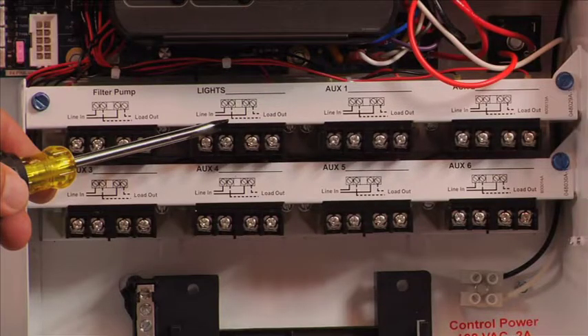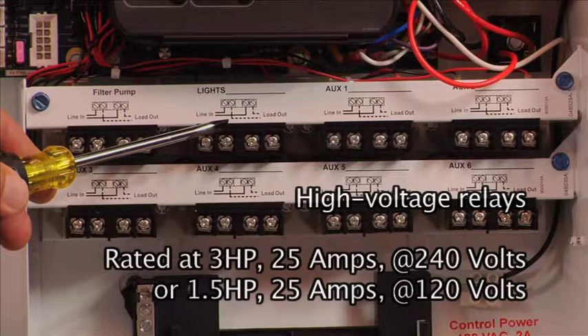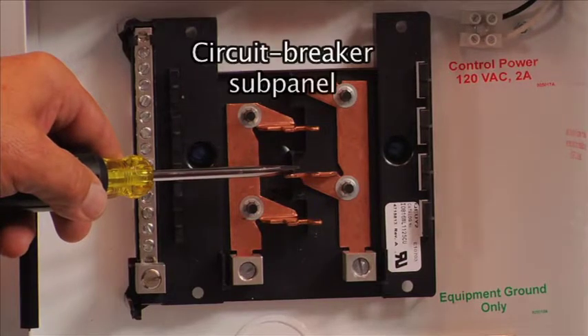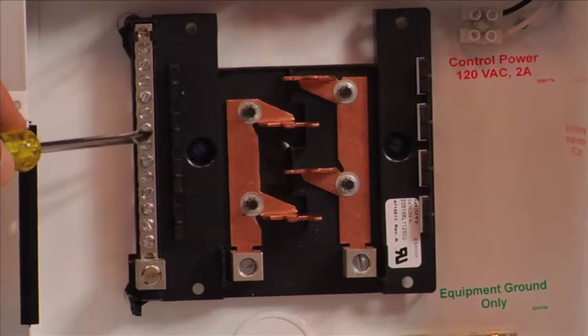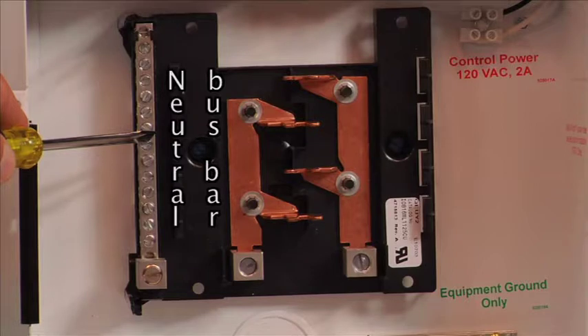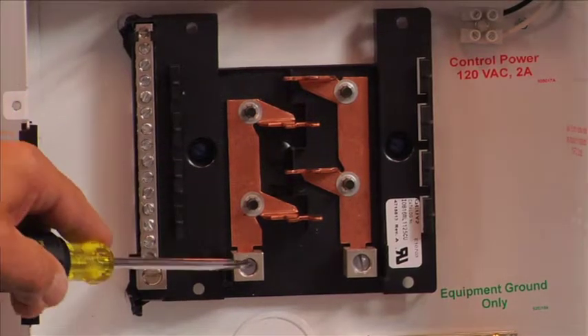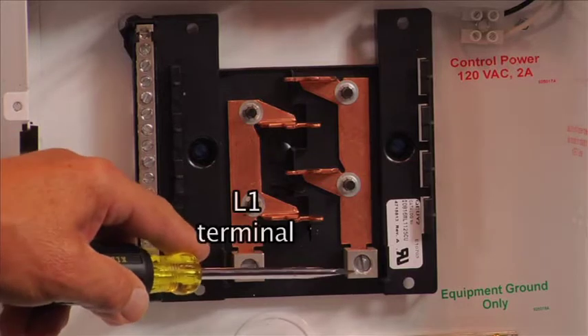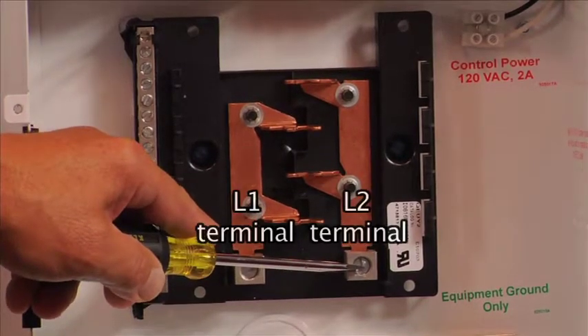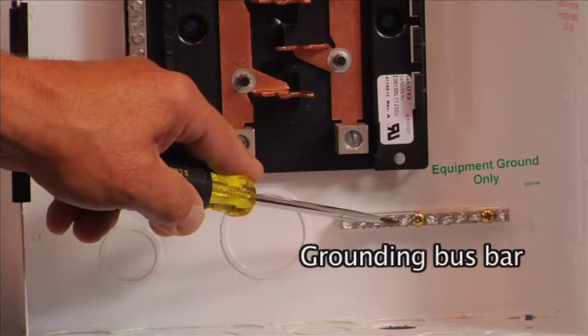Below the PCB are the high voltage relays. These relays are rated at 3 horsepower 25 amps at 240 volts or 1.5 horsepower 25 amps at 120 volts. Below the high voltage relays, you will find the circuit breaker subpanel. The subpanel consists of breaker positions and is rated for 100 amps maximum. Mounted on the left side of the subpanel is the neutral bus bar. At the bottom of the subpanel are terminals L1 and L2 for connecting 240 volts AC to the control box. Below the subpanel is the grounding bus bar.